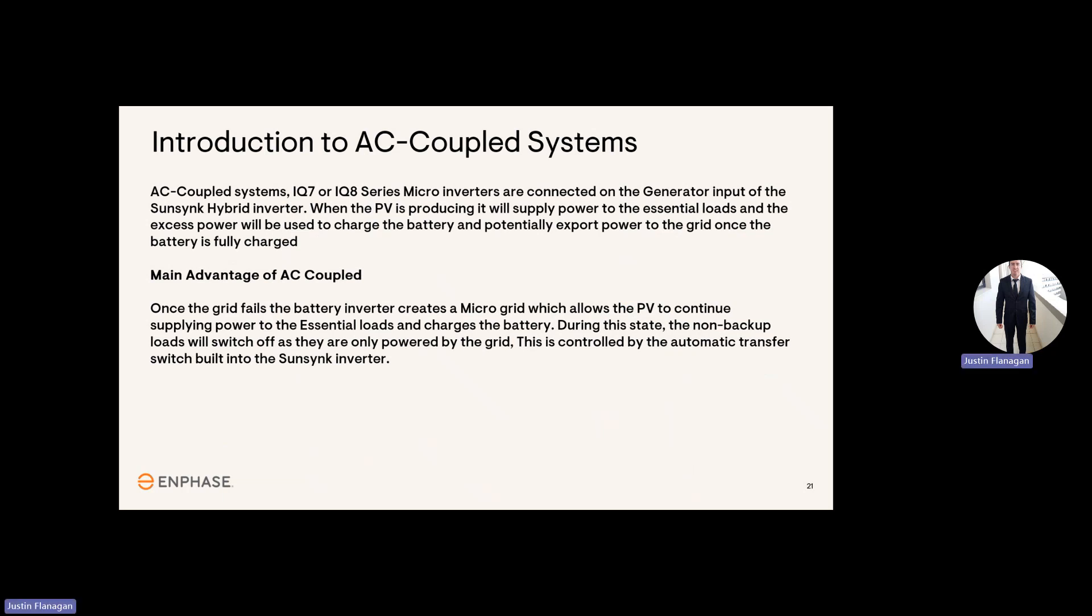So just an introduction to the AC-coupled systems. What is meant with AC-coupled? AC-coupled systems, IQ7 or IQ8 series microinverters, are connected to the generator input of the Sunsynk hybrid inverter. When the PV is producing, it will supply power to the essential loads, and excess power will be used to charge the battery, and potentially export power to the grid once the battery is fully charged.